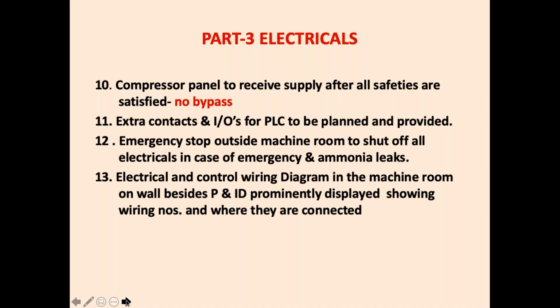So it is very, very important that unless all the safeties in the system are not bypassed and the green light lights up showing that all safeties are operating, the compressor should not be started. This is very important. Don't bypass any of the safeties. Go to the root cause why the safety is cutting out, either discharge temperature cut out, LP cut out, HP cut out, oil pressure cut out, they are tripping. And remove the problem, don't bypass them. Emergency stop button, I already told you, outside the machine room, inside the machine room is essential.